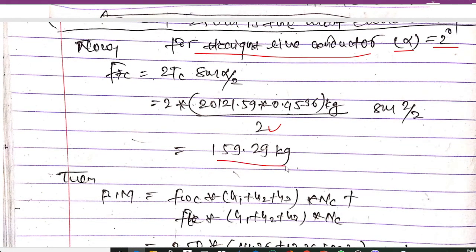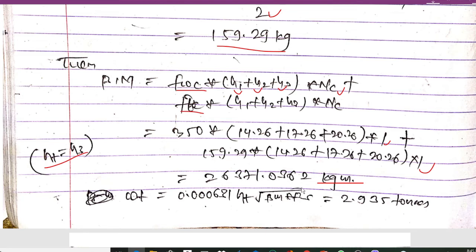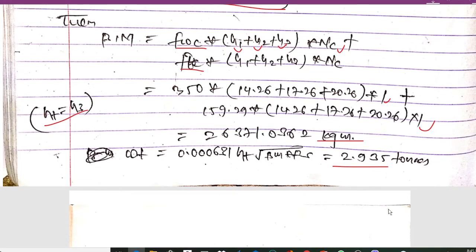The bending moment is: BM = Fwc × (S1 + S2 + S3) × nc + Ftc × (S1 + S2 + S3) × nc, where nc (number of circuits) = 1. Substituting the calculated values of Fwc = 350 kg, Ftc = 159.29 kg, and the S values gives a bending moment of 26371.0362 kg·m. The tower weight is then calculated using: W = 0.000631 × ST × √(BM × UTS / safety factor), yielding W = 2.935 tons for the 250-meter span.